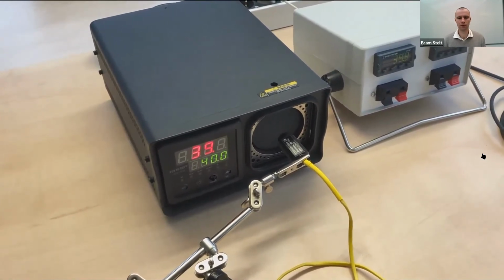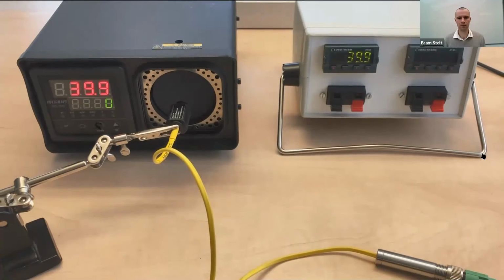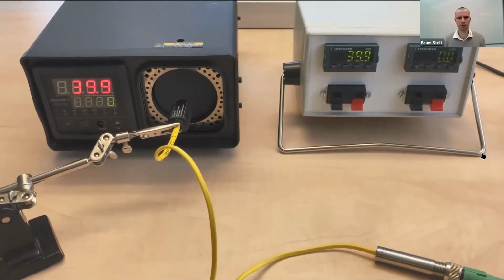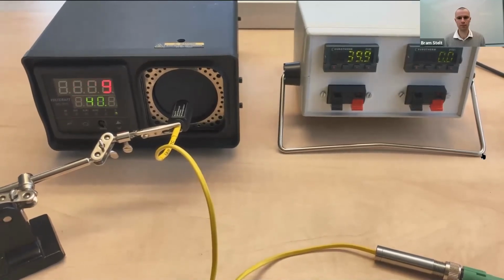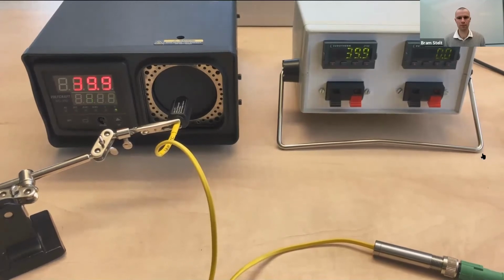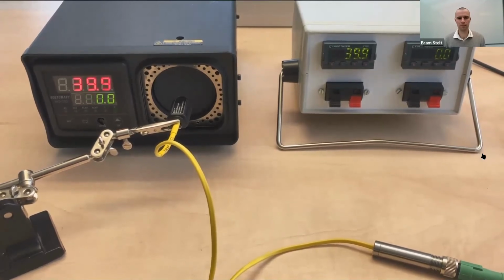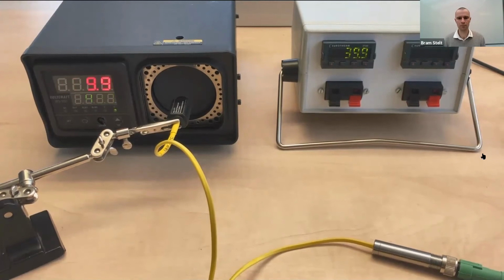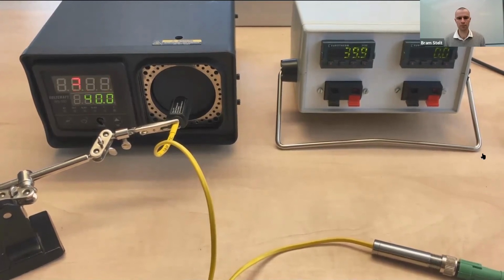So if you order an AutoSmart sensor with a standard calibration, so minus 30 to 70 degrees C, or 0 to 100 C, or 0 to 250 C, this is how it works. There's also a possibility to do a custom calibration. Let me demonstrate to you how that works.